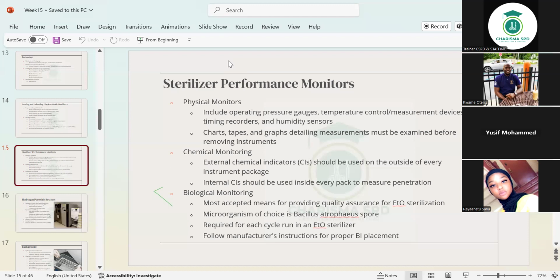So you see that with the ETO, every cycle in the ETO has to go with a biological monitoring device, which is the BI. So the ETO, you have to be very careful with it and have to do that. Even without the ETO, other low temperature sterilization, some systems, some facilities, make sure you add BI all the time. Okay? To be very sure that they're getting what they want. They're getting the sterility that they need. Any questions?